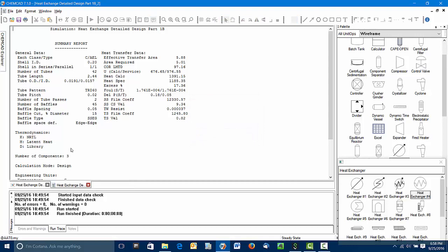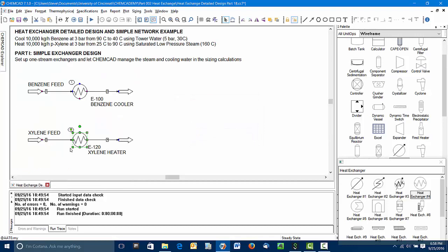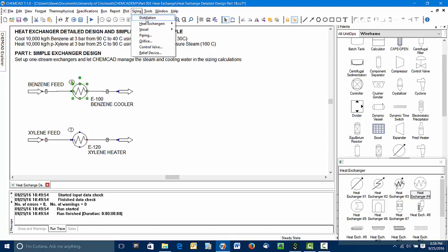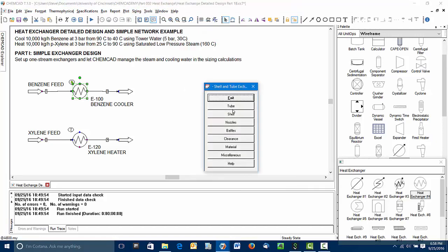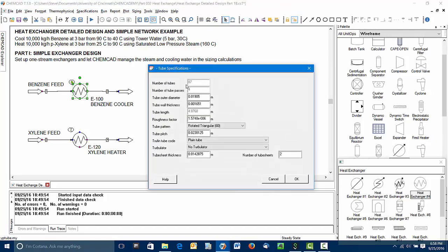So with that, we've done detailed designs of these two exchangers. We now could go back in there. We can get tube counts. Let's just go back to sizing for a moment. I'll show you that. It's available in the TEMA sheet. You can look at the exchanger geometry. You can see there's 87 tubes, four tube passes. The tubes are 4.8 meters long. These are all results of the ChemCAD calculation.